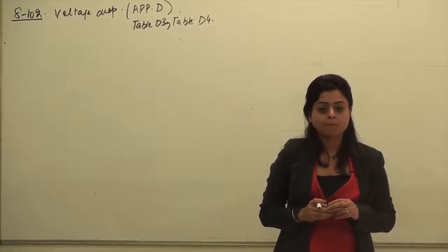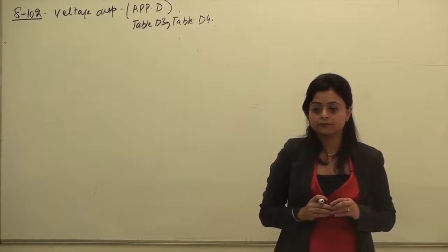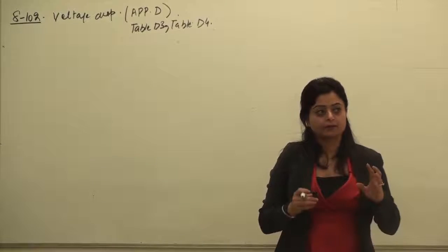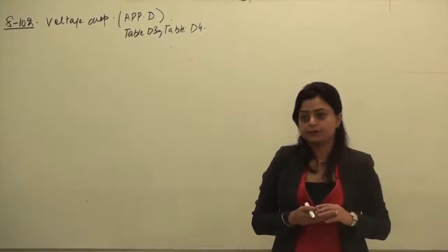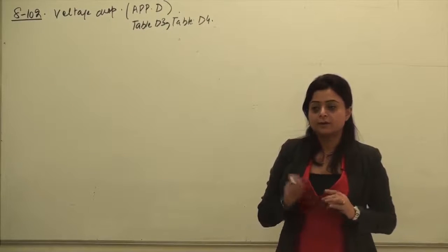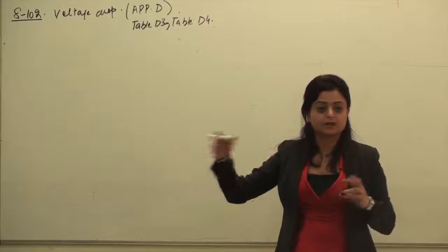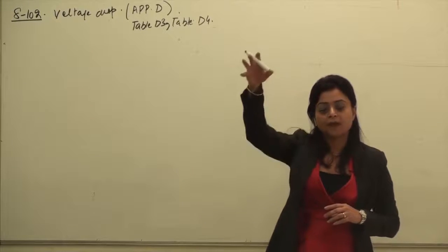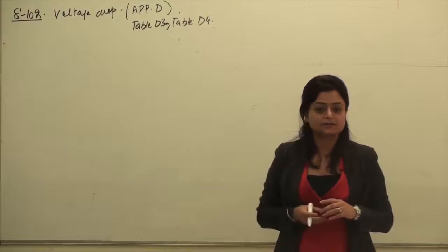Now, what do we need? We need to understand from the pole to this receptacle, if the pole gives 120 volts, by the time it gets to the receptacle, how much drop is allowed? Okay? Or from the panel to this receptacle, how much is allowed?